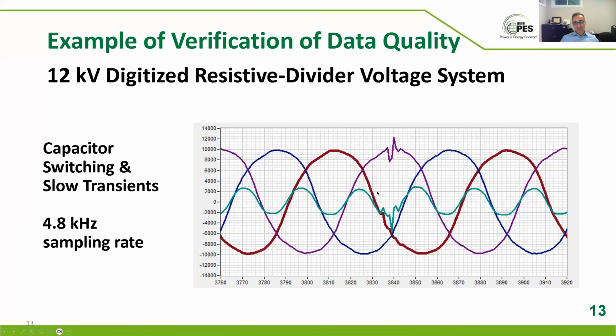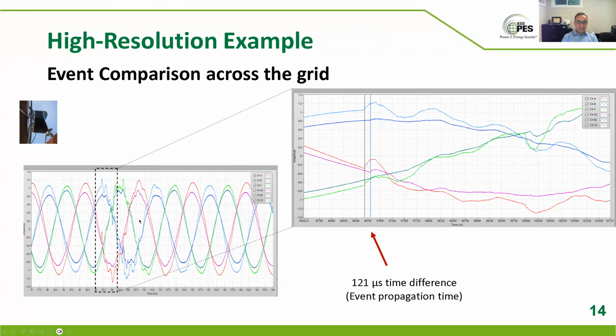That was one application. They also verified that they could see a switching transient on both sensors and say, yeah, you could get the switching transients they were looking for. Of course, this was only 4.8 kilohertz, so by nature, this should be a little bit filtered, but that was good. Let's jump to what's a bit closer to heart for me, and it's a bit higher frequency, a higher resolution. And that's sort of a bit of event comparison.